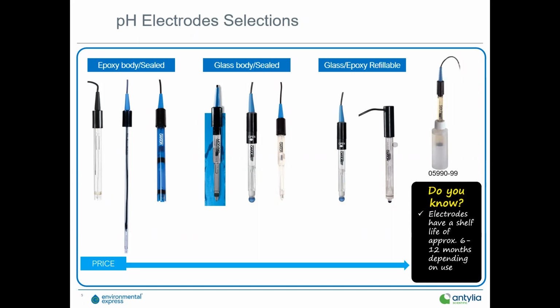The center grouping is the glass body electrodes. The first one is a spear tip electrode. The middle sensor is a large glass bulb with annular junction. It's a ceramic junction. That's a great sensor for low ionic strength solutions. You get enough electrolyte to leach into the solution or sample you're measuring to get a stable reading. And then finally, the third guy is also a glass electrode with a spear tip on it.